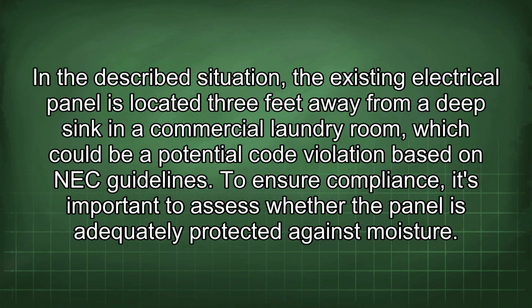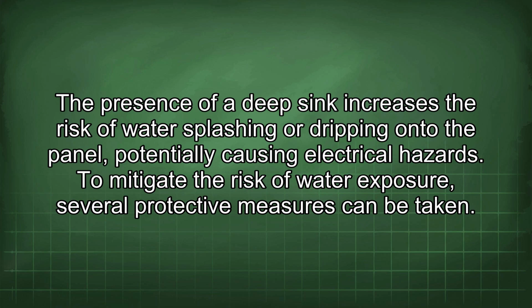In the described situation, the existing electrical panel is located 3 feet away from a deep sink in a commercial laundry room, which could be a potential code violation based on NEC guidelines. To ensure compliance, it's important to assess whether the panel is adequately protected against moisture. The presence of a deep sink increases the risk of water splashing or dripping onto the panel, potentially causing electrical hazards. To mitigate the risk of water exposure, several protective measures can be taken.